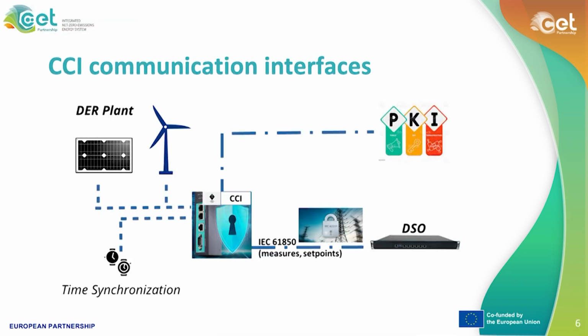Regarding the communication interface, the norms prescribe the communication between the DER and the distribution system operators using the IEC 61850 standard for sending measures and receiving set points. We require specific semantic data models and services defined in the 61850 series, and their security is assured by the application of the IEC 62351 standards and related parts.